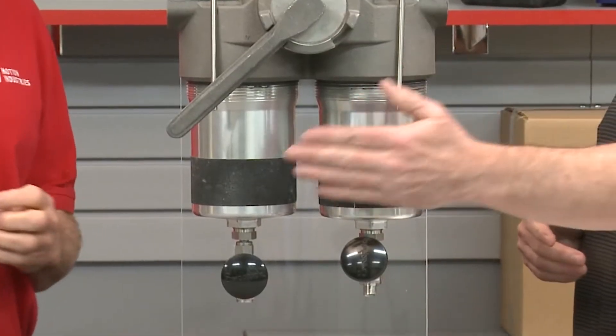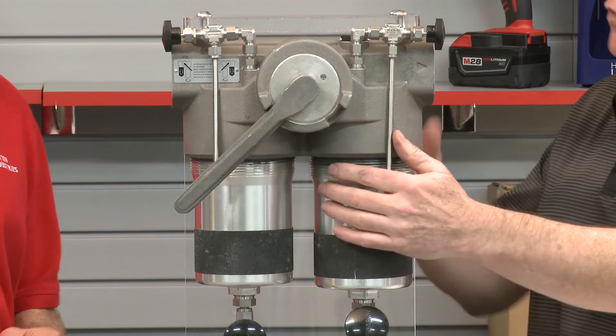A duplex filter has twin filter bowls and often includes a switchover lever that allows you to change the flow of the liquid from one side of the filter to the other. The advantage is that you can change a filter element by isolating it from fluid flow, and the hydraulic system can continue to run while you do so.